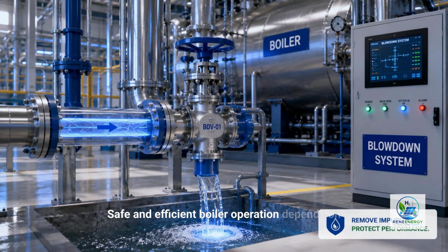Safe and efficient boiler operation depends on continuous measurement. Pressure transmitters, temperature sensors, flow meters, and level instruments constantly monitor every critical operating condition throughout the plant. These instruments transform physical measurements into digital information that operators and control systems can use to make real-time decisions. If pressure changes, water levels fluctuate, or steam demand increases, the instrumentation immediately detects the change. This continuous stream of data allows the boiler to respond automatically, maintaining stable operation while maximizing efficiency and protecting equipment from abnormal conditions.